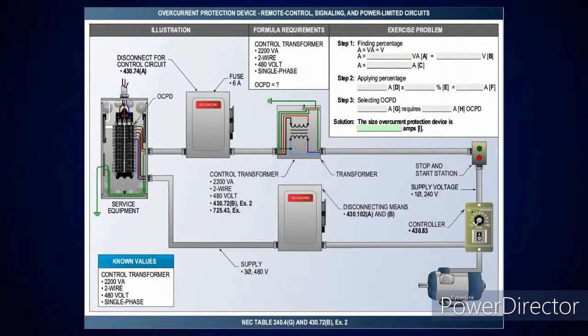And then you've got the same thing here. You've got your control conductors, and you've got a control transformer there. Well, what do I have? I have a 2200 VA transformer. It's 480 volts. You're going to divide that, get your amperage, then you're going to go look at table 450.3B to get the percentage. So in this case, if I was below 2 amps, then I'd take it at 300%. See that? And that's where you're going to look at table 450.3B. But I'll point out again, you're going to notice there's no superscript 1. Now, if I'm over 9 amps, then you take it at 125%, and guess what's there? A superscript 1, which means I go up to the next standard size.